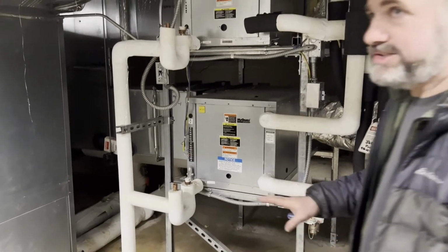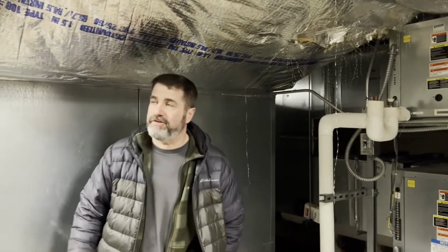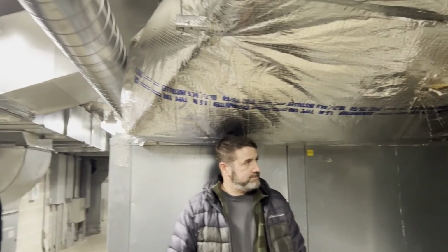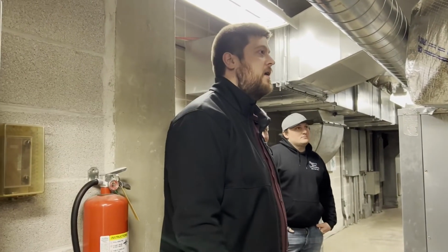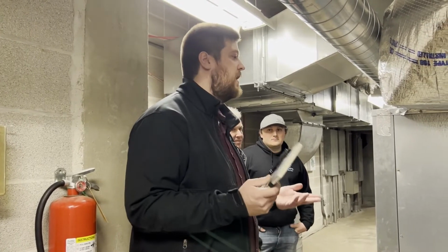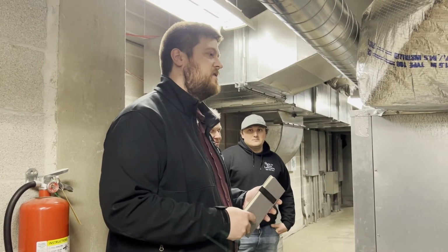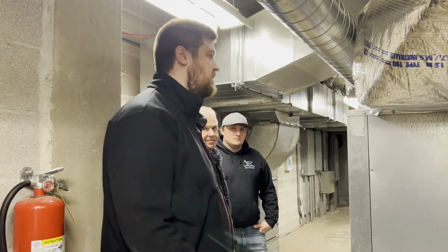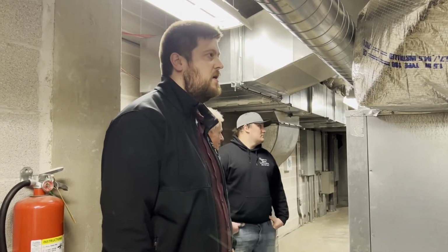It's kind of a dumb question, but what part of the pump fails? Is it consistently the same part that fails? We get a lot of control issues, which is obviously tied into our building automation system. This is actually the brain of the building here between these two. A lot of times it's the compressors inside. We get all kinds of glycol issues with the pumps inside. Sometimes it's just an electrical issue. Especially when we have big storms, a lot of times we'll get surges, and there's all kinds of stuff in place to protect those things, but we still sometimes get electrical issues with them.